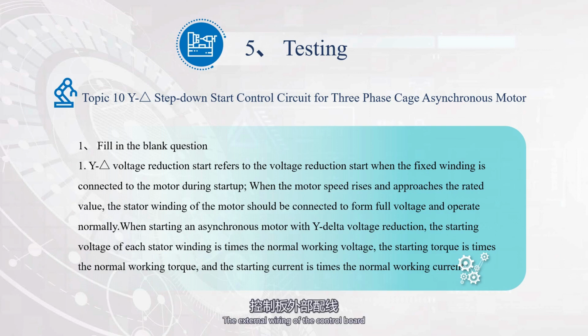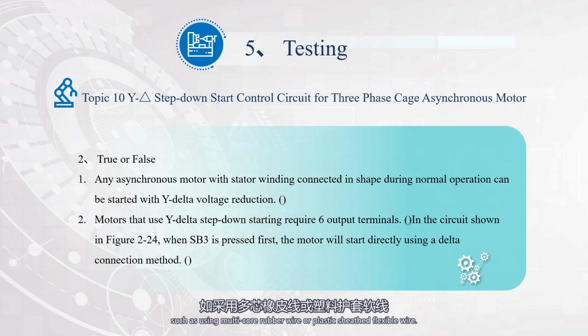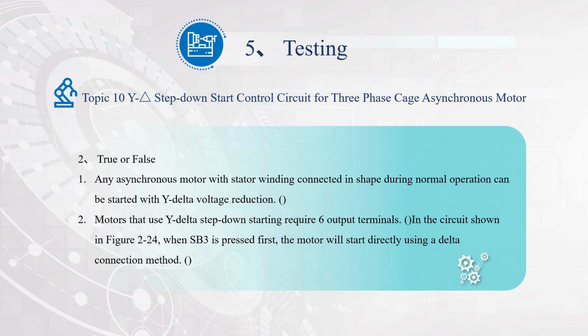4. The external wiring of the control board must be installed in the wire channel as required, so that the wires have appropriate mechanical protection to prevent the invasion of liquids, iron filings, and dust. During training, the requirements can be appropriately reduced but must be based on conditions that ensure safety, such as using multi-core rubber wire or plastic sheath flexible wire. 5. Before powering on the calibration, it is necessary to double-check whether the fuse specifications and the setting values of the time relay and thermal relay meet the requirements.